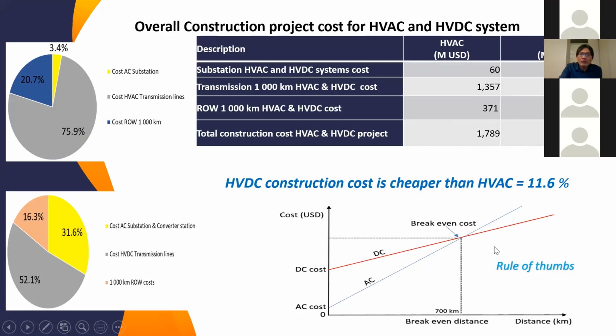From the diagram here, by rule of thumb, we can see AC substation cost in the beginning is very low, while for DC it is high because we have the cost of converter station. But because the transmission cost and right of way cost for DC are smaller, at the end for 1,000 kilometer you can see we have 11.6% cheaper than AC. Based on rule of thumb, normally they say the break-even distance is within 700 kilometer for overhead line, and between 40 to 50 kilometer for cable.